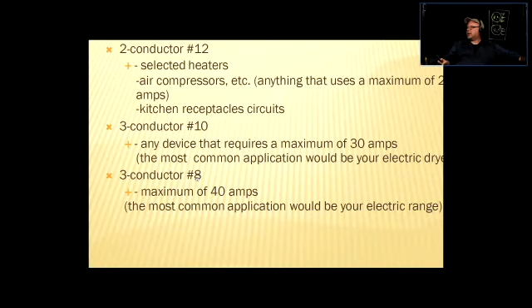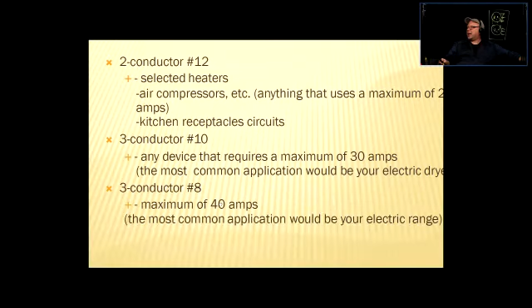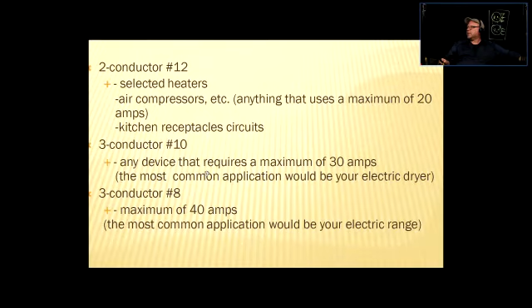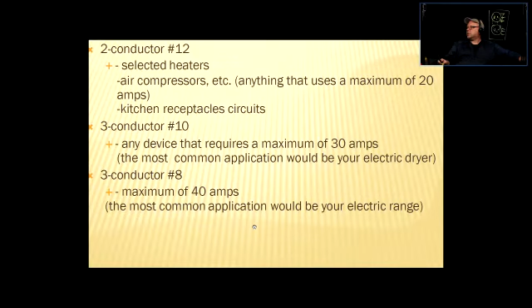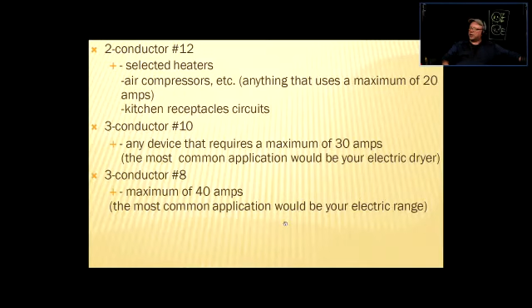So number 8, the gauge number goes down, the thickness of the wire goes up, and of course there's more amps. 40, 30, 20, 15. Okay, so for the three conductors, number 8, the most common application would be the electric range. Electric range is just another way of calling a stove.